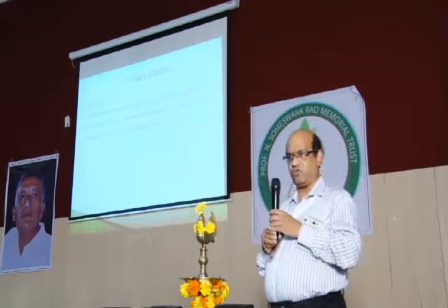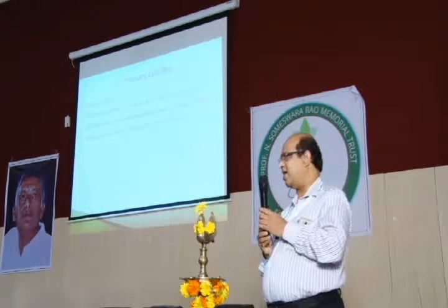Then, after that, the neutralization tank, as discussed, is also required where we have to do acid dosing or base dosing. All the effluents will not be at pH 7, so we have to add acid or base, or sometimes we have to add a coagulant or flocculant also, in the neutralization stage. Then the primary clarifier, as you know very well, is a type 2 settling.